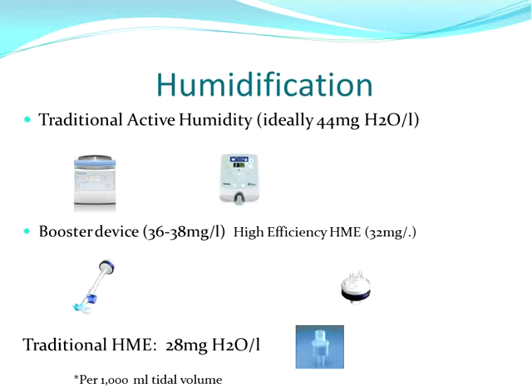One of the things that we maybe don't like to think about with traditional active humidity is that if we aren't setting those optimally, we aren't getting optimal humidification. So turning the temperature way down to help decrease the amount of rain out that we have in tubings and those kinds of things actually can decrease the amount of humidification that the patient's getting. So looking at that and recognizing, number one, do we need or do we want ideal humidification, optimal humidification for at least some hours of the day, or is the patient going to tolerate being off of that?